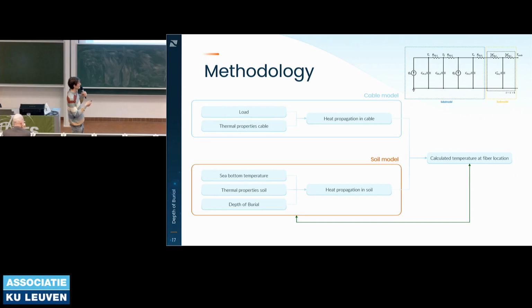So we use quite a bit of combinations, and we end up with quite a few possibilities of the fiber temperature, which we compare with the real measurements. The combination that gives the best fit tells us which soil properties there effectively are, and what the depth of burial of the cable is. That's our depth of burial model in a nutshell.